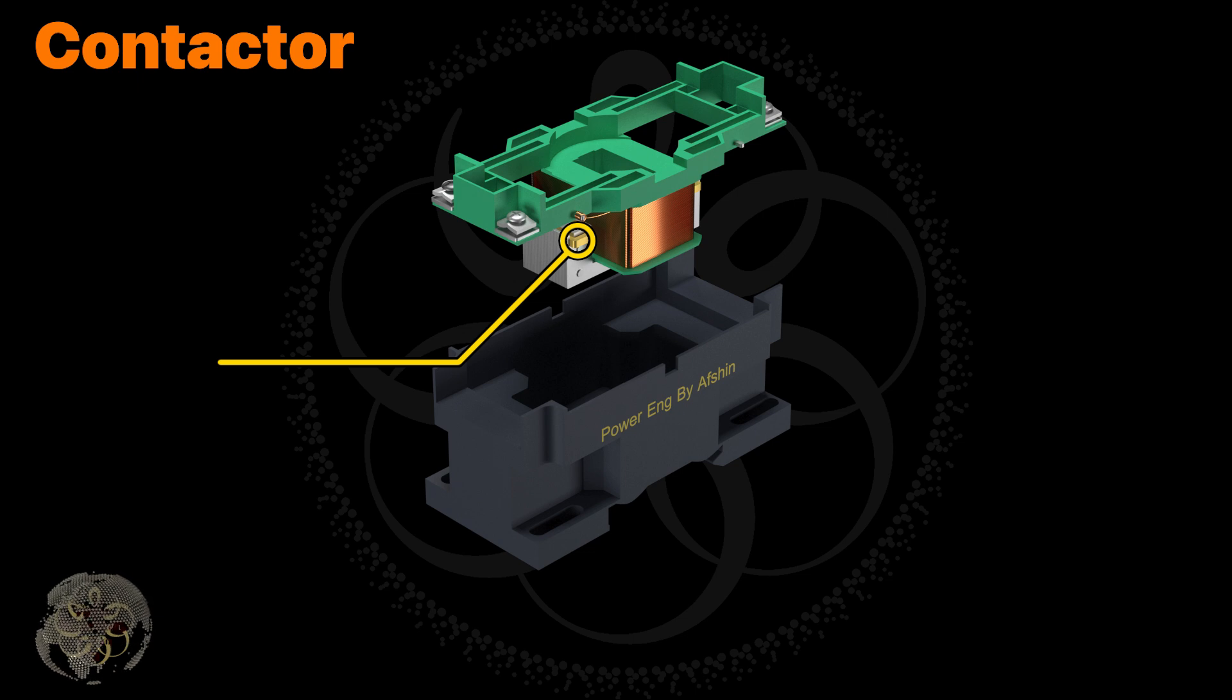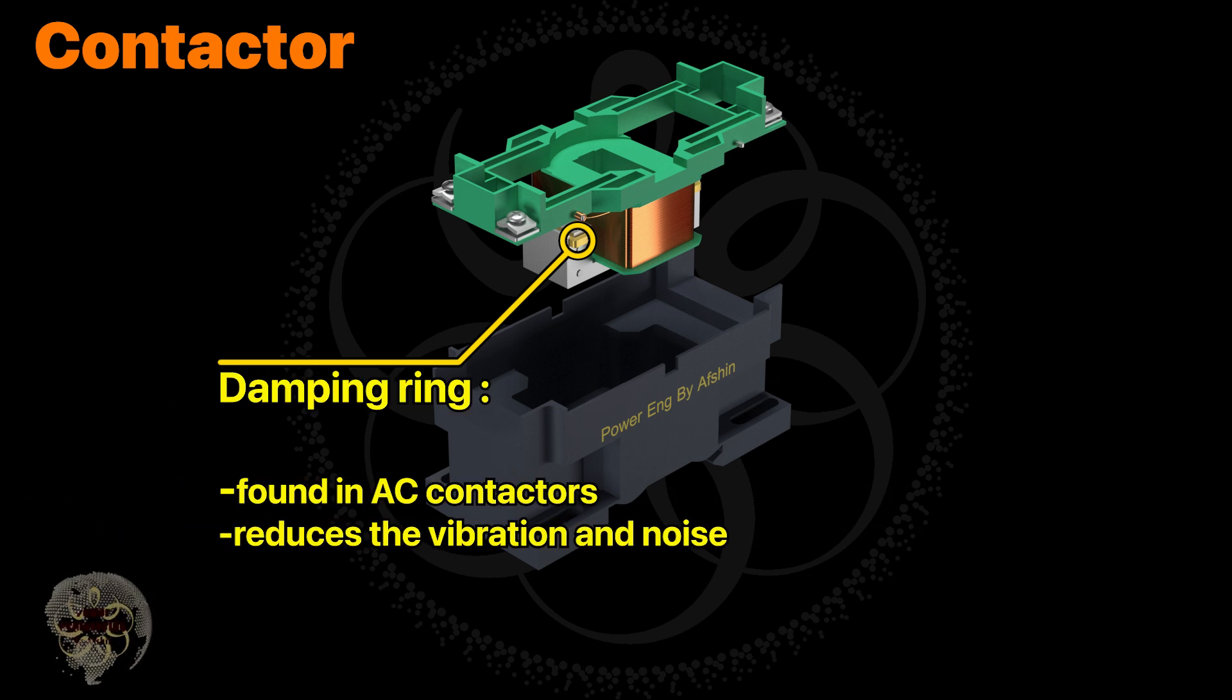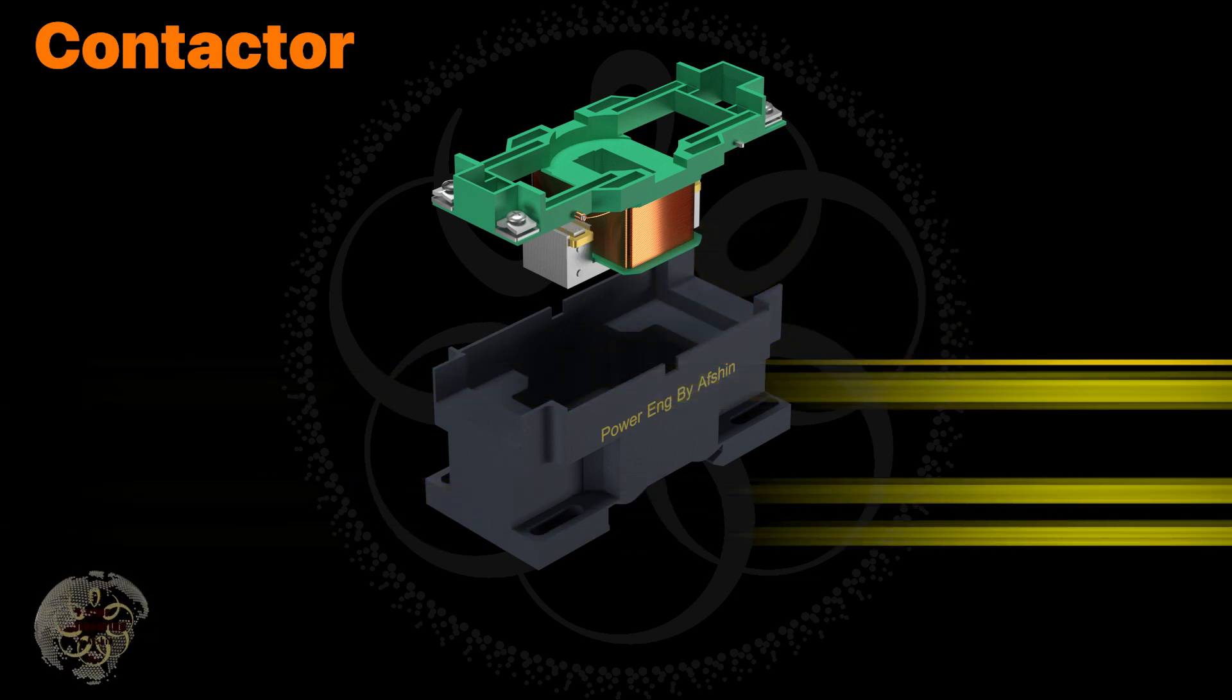The damping ring is typically found in AC contactors and reduces the vibration and noise caused by the alternating magnetic field. This ring ensures that the magnetic flux through it is not in the same phase as the flux in the core. As a result, when the core's flux passes through zero, the flux in the ring helps stabilize the armature.